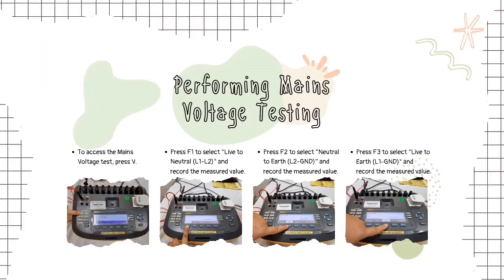Then, for performing mains voltage testing, we must access the mains voltage test by pressing the V button. First, press F1 to select live to neutral, L1, L2, and record the measured value. And then, select neutral to earth, L2 to GND, and record the measured value. And then press F3 to select live to earth, L1 to GND, and record the measured value.